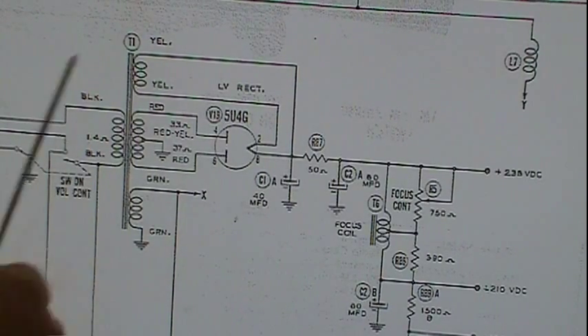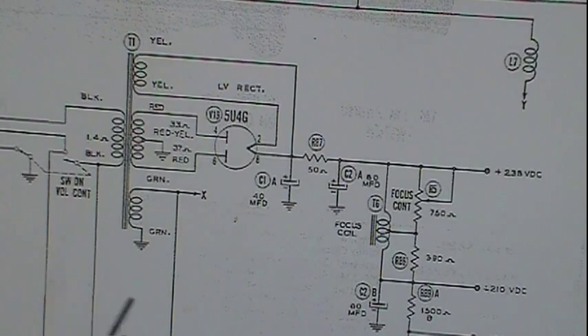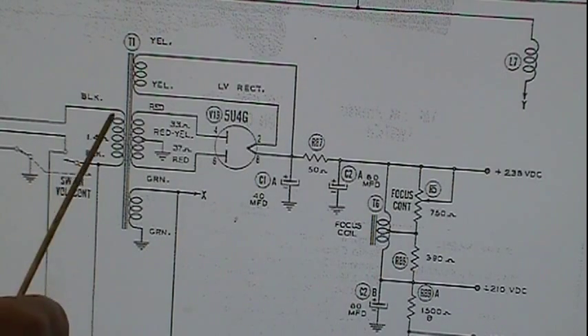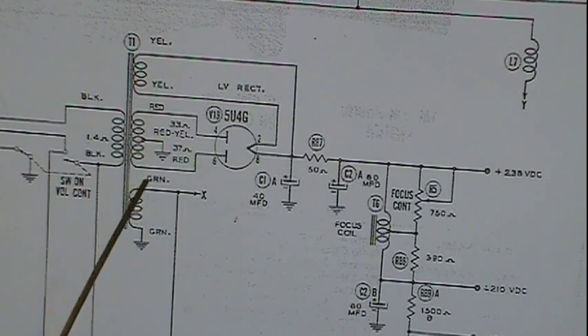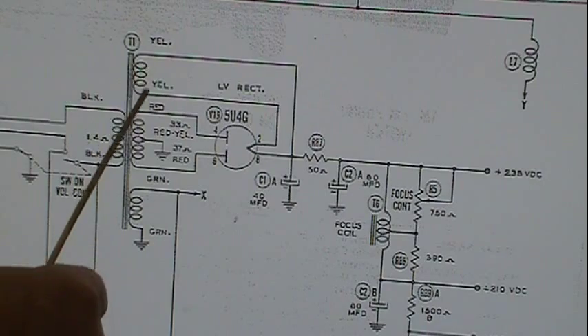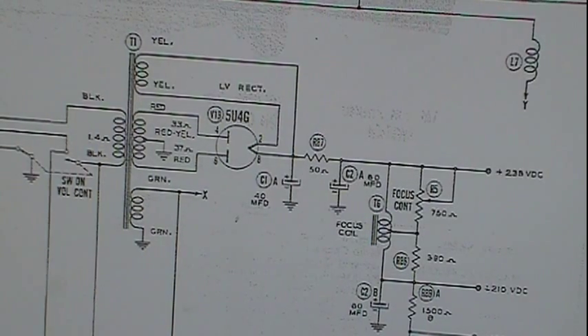So any power transformer is the same thing, built this way. Now, auto transformers are different. But here you've got an actual separate winding for your primary, a separate winding for your high voltage, a separate winding for your 6.3, and a separate winding for your 5 volt if you need it.